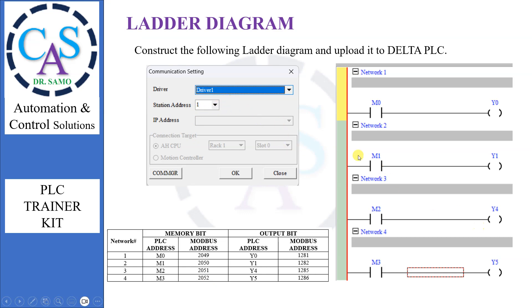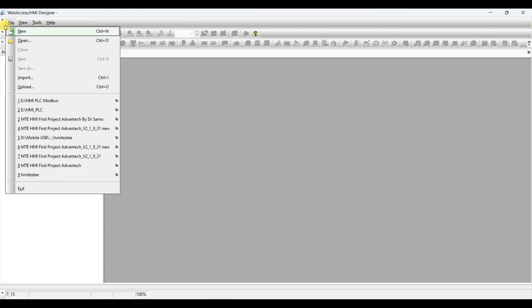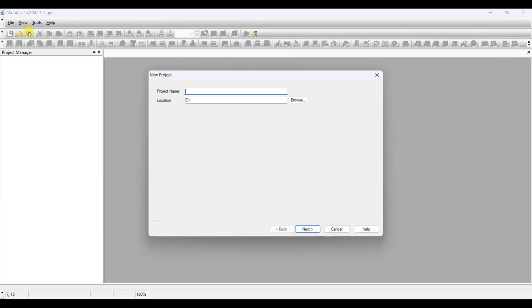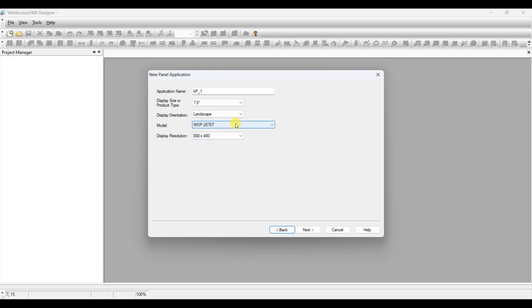Now it's time to design HMI. For designing HMI, open WebAccess/HMI Designer Software. From the file menu, select a new file, assign a name, and click next. Set parameters: Application name is AP1, display size or product type is 7 inch. Remember, if you do not select the proper display size, your HMI model will not be displayed. After that, set display orientation as landscape, model as WOP-2070T, and display resolution as 800x480. Press next.